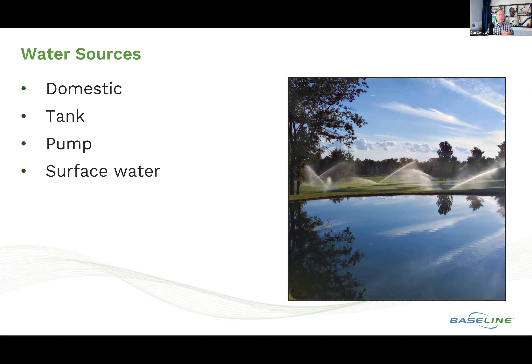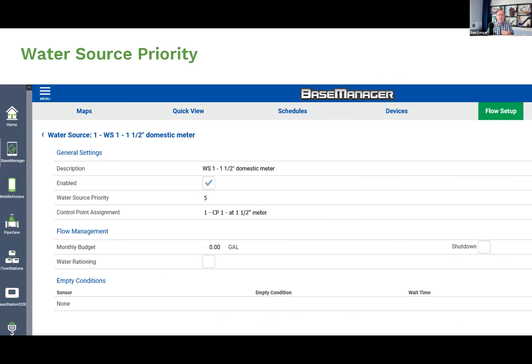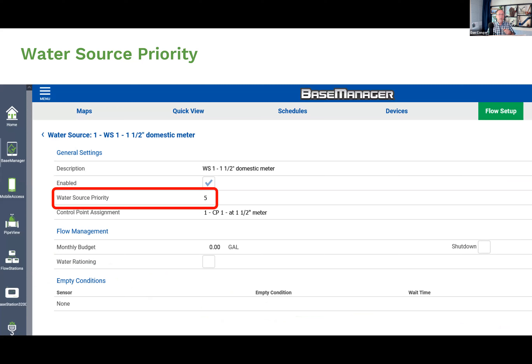If you have multiple water sources, you may want to prioritize them — rank them one over another. In Base Manager, I'm showing a water source that's an inch-and-a-half domestic meter ranked at water source priority five. If I have eight different water sources, I can rank them from highest to lowest: the lowest number is the first one I'll use, and I work sequentially through them.